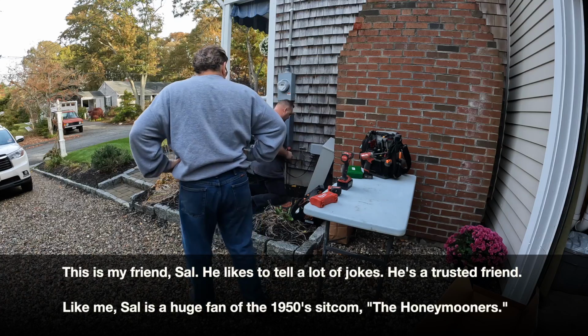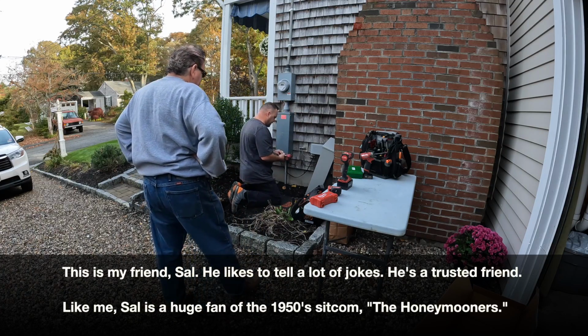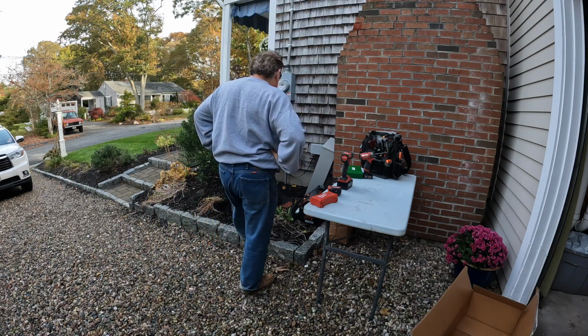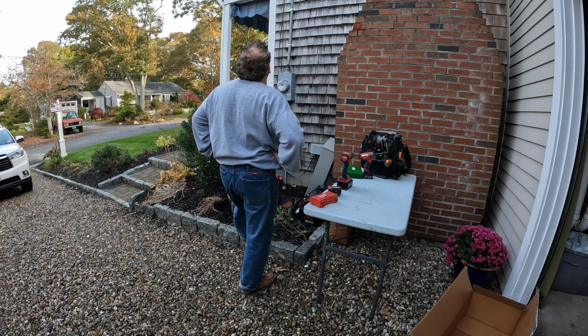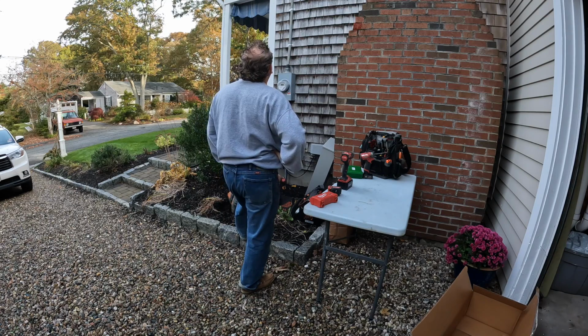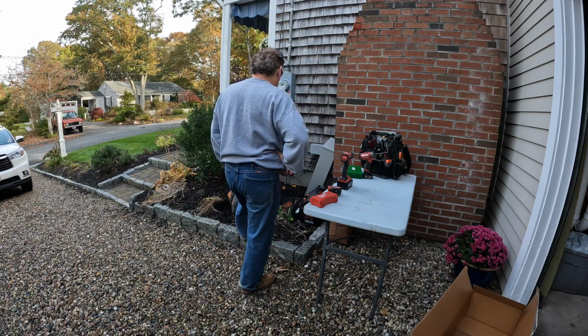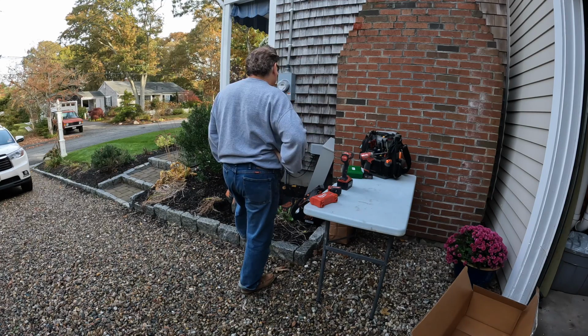Well, you see, this is the grounding electrode conductor. And if something's not bonded correctly, this could become energized. Especially if that bare wire becomes disconnected from there out to where it connects on the street, then the return current would flow on this. But it's pointy, right? So you think you're getting shot.